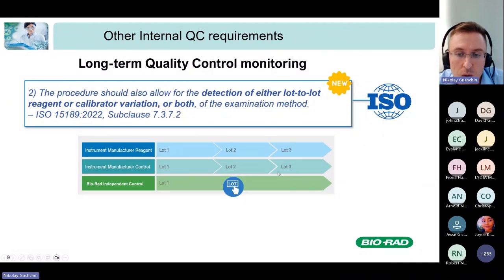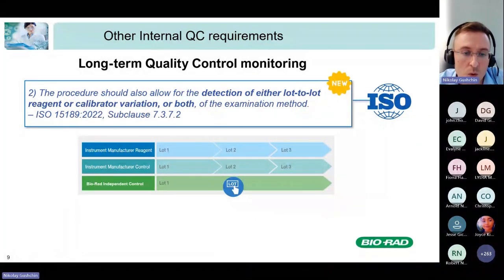period, there can be some changes in other components of your test system, like changes in the reagent lot or changes in the lot of the calibrator. But the shelf life of the control material overlaps all these other components' shelf lives. And this can give you an understanding of what is going on in your test system, what is going on with the results, every time you have a change in the reagent or calibrator or some other component or diluent, for example.